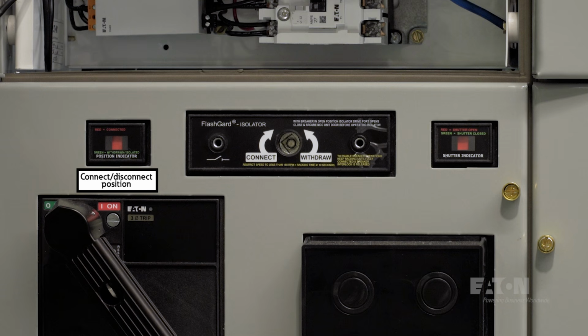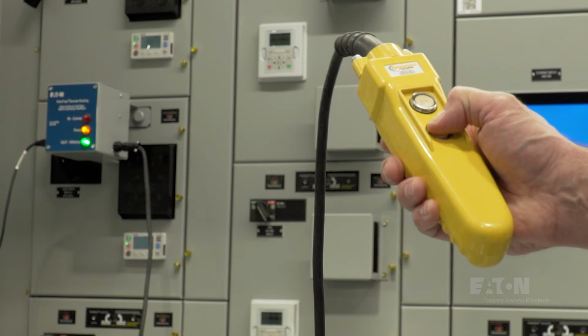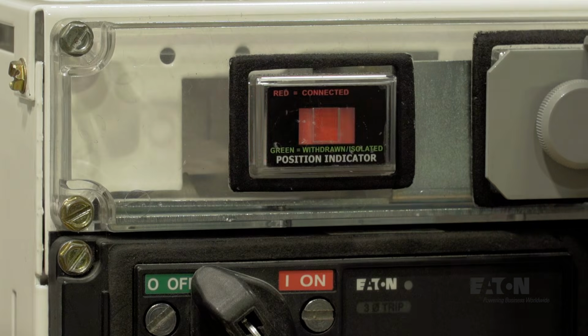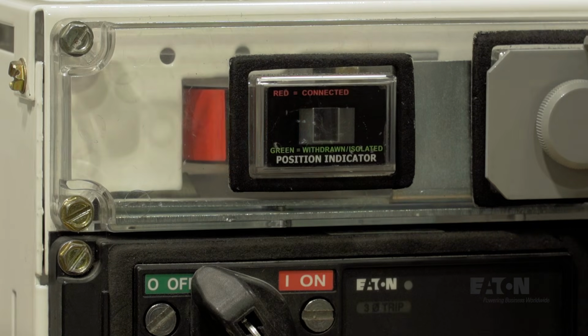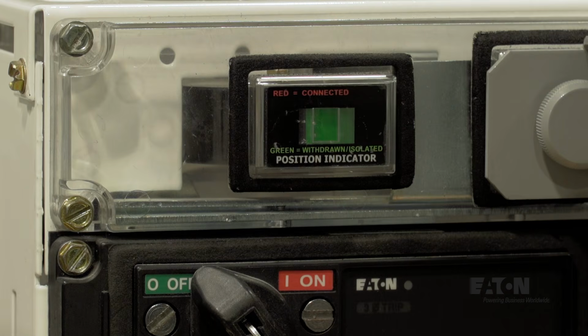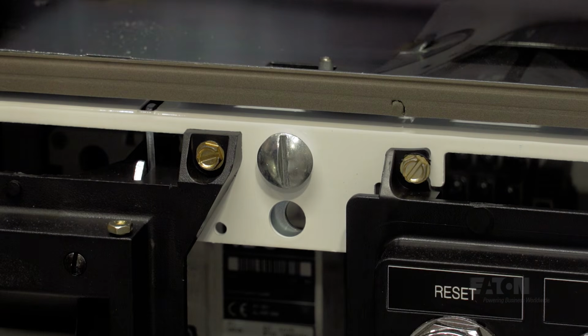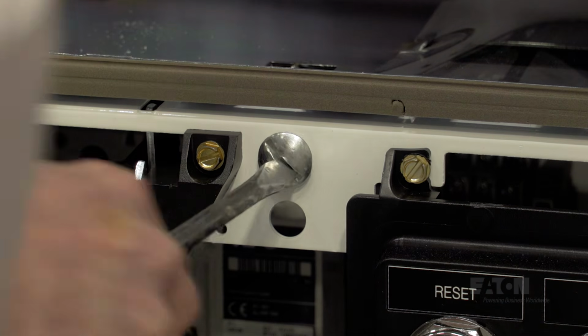A visual indication is provided on the unit door showing the connect and disconnect positions of the RotoTrack, as well as the position of the shutters that enclose the stabs. The bucket can be racked manually or remotely using a wired pendant that is attached to a RotoTrack remote operator, allowing the operator to be outside the arc flash boundary. The unit wrapper is equipped with a quarter-turn side wrapper latch that securely holds the unit to the compartment. The latch can only be engaged when the stabs are fully mated with the vertical bus.